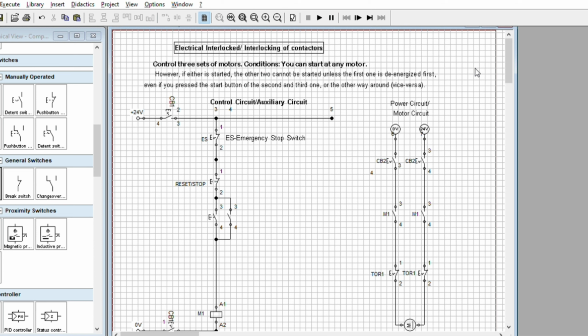So this is double electrical interlock with 3 motors. As you can see here, we have a normal start stop. We'll add an overload relay later. And we have 1 motor, so we'll need 2 more motors because there are 3 motors here. We cannot start the other 2 unless the first one is de-energized first. But you can start at any motor.